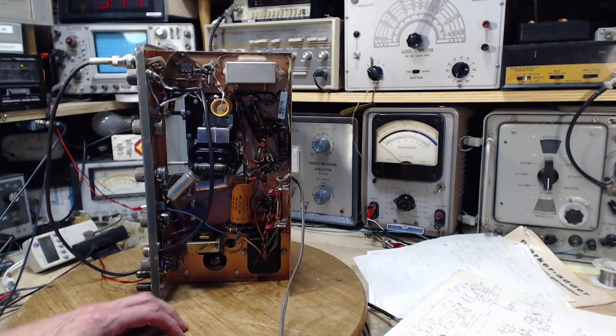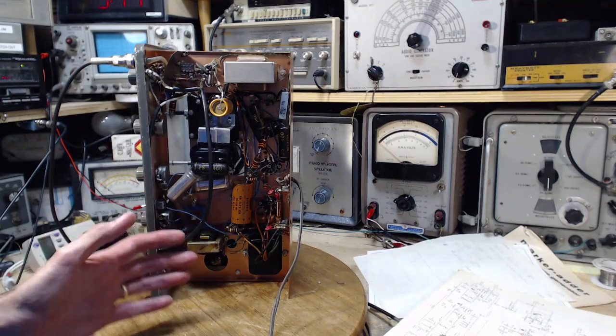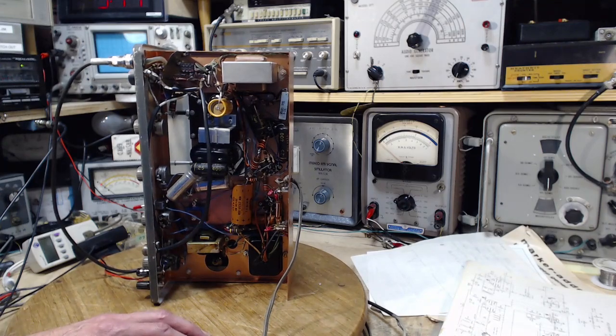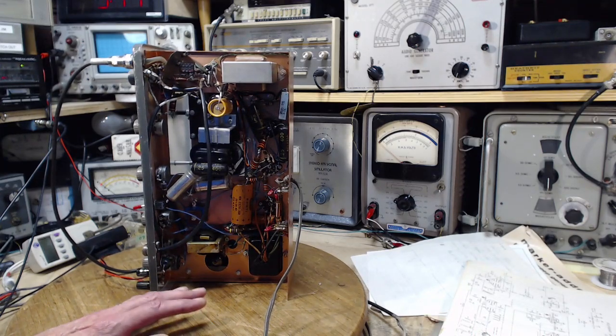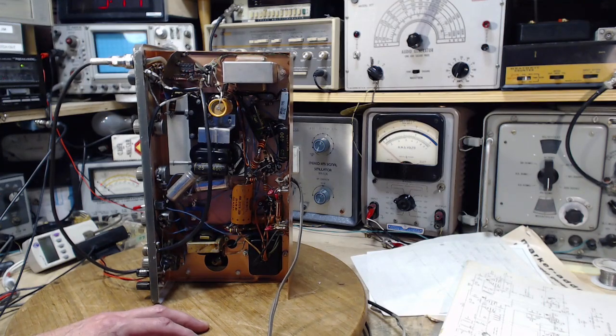Holy smokes. So we go to the vault. We're standing on top of it, and this thing is just roaring inside. And I'm panicked. I don't want to go in this vault. Down we go, and we spent a couple minutes in there because I couldn't stand it. Transformers humming away, overheating, no load on it whatsoever. And they turn to me and they go, "Do you know why this is happening?" I gave them that whole explanation.